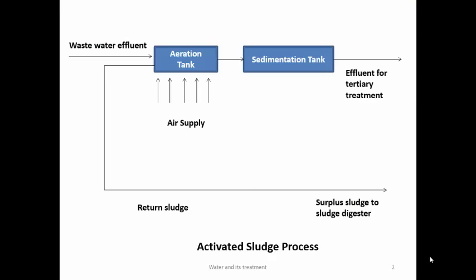Activated sludge method: wastewater from sedimentation is passed through an aeration tank where air is passed to oxidize organic matter. This process is slow but is fastened by using sludge from the previous oxidation — which contains numerous bacteria, hence called activated sludge. The mixture is kept for 6–8 hours with air passing through. Aerobic bacteria in the sludge carry out oxidation of organic matter. The treated water goes to a sedimentation tank and finally to tertiary treatment. Some sludge is used as fertilizer; part is sent to sludge digester; and part is recycled to the aeration tank as activated sludge for fresh sewage.